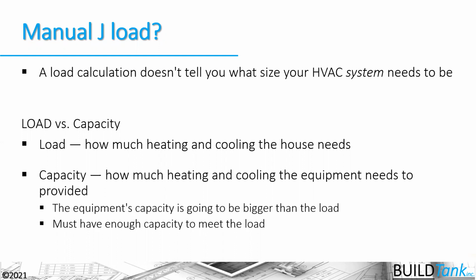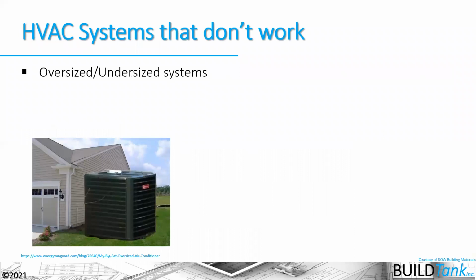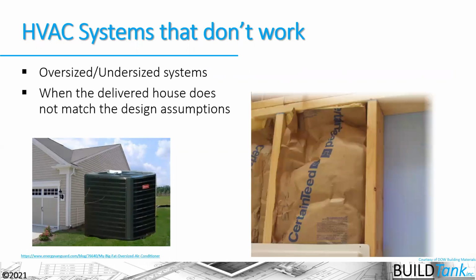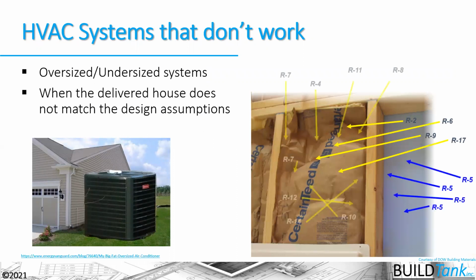and will not be meeting the true load requirements of that house there. So we want to not only define the load for the house, which is what the manual J is doing, but we want to pick the equipment in manual S that has the proper capacity to meet that load under worst case conditions there. So again, it's going to be slightly oversized, but we don't want it to be significantly or drastically or grossly oversized equipment here. So we have potentially oversized systems or undersized systems in our houses, often because our thermal envelope isn't being executed as it was supposed to be executed there.